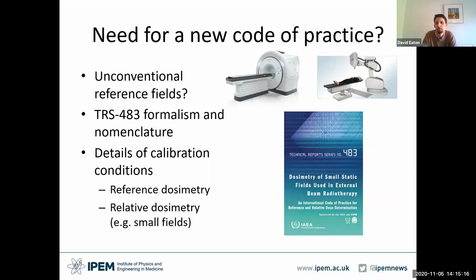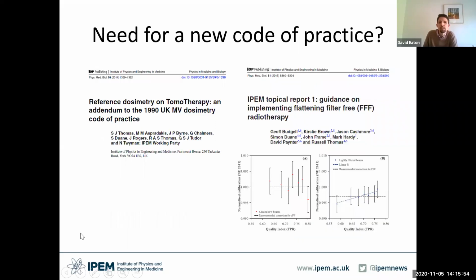There's also been a major report published by the IAEA, report 483, which looks particularly at small fields and brings in a lot of formalism and nomenclature from previous works to try and more accurately define different types of calibration field. And it was also recognised that the 1990 code was pleasingly short, nice to read if you're a trainee, it's only about 4 pages long, but it was a little bit brief on guidance on calibration conditions, both in reference dosimetry, but also in relative dosimetry as well, for example, many small fields. So on this basis, there were some addendums and additions which were brought out in the meantime. There was an addendum to specifically address tomotherapy back in 2014.